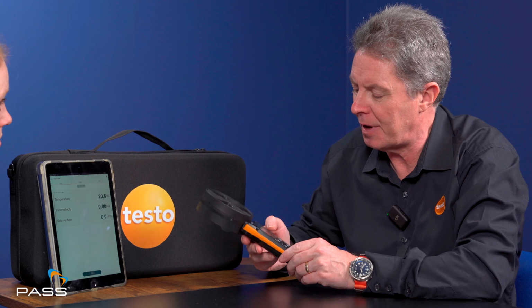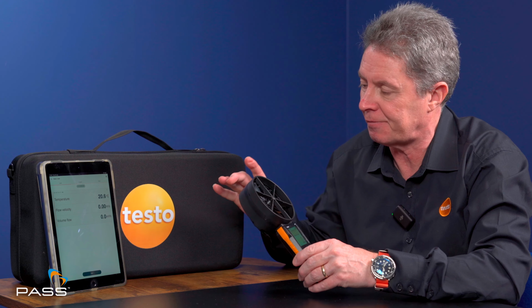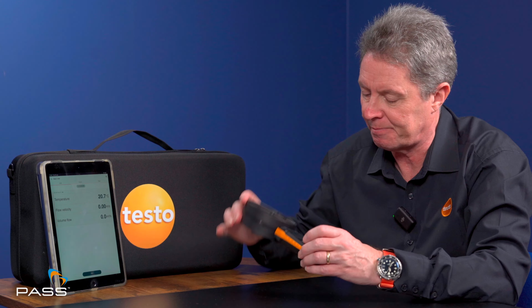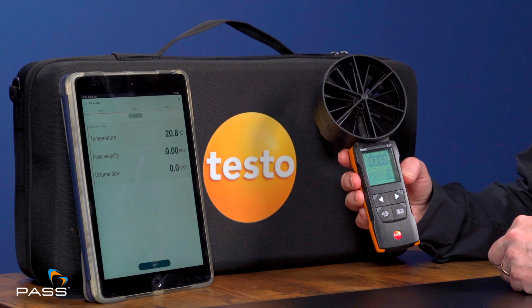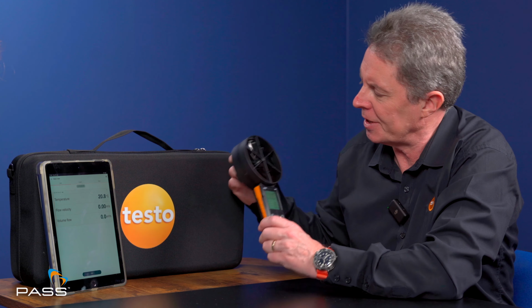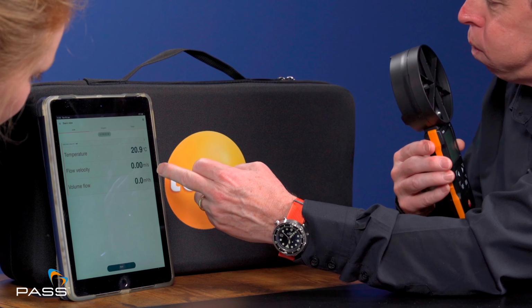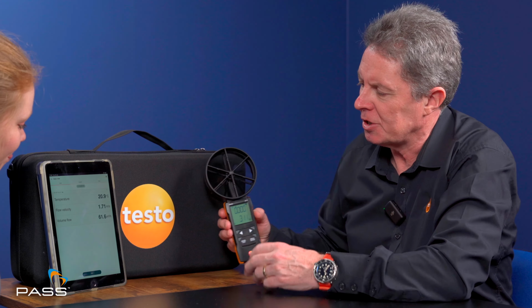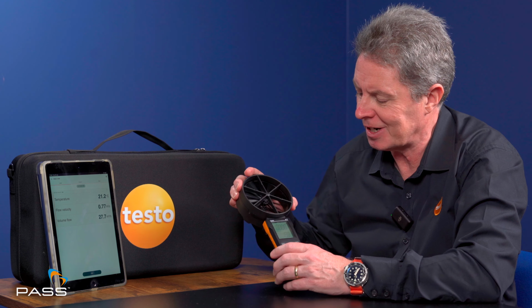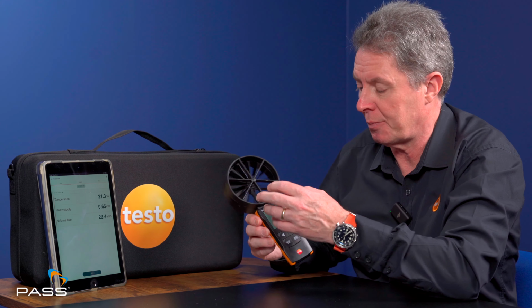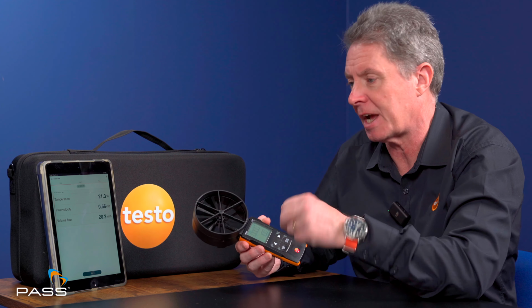You can also program the device for the characteristics of the outlet geometry, the size of it. The other option, because this device has Bluetooth, is to use the Testo Smart app. We've got the display here, but also the same information relayed across the Smart app. If I create some airflow, you can see we now get the actual information - it's all about capturing information in a much more effective, digital way, which can be put into a report. Someone can use this without the Smart app and just write readings down, but it's much better to get the digital reporting you get with the Smart app.